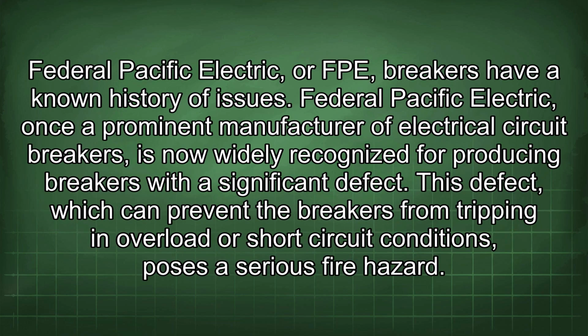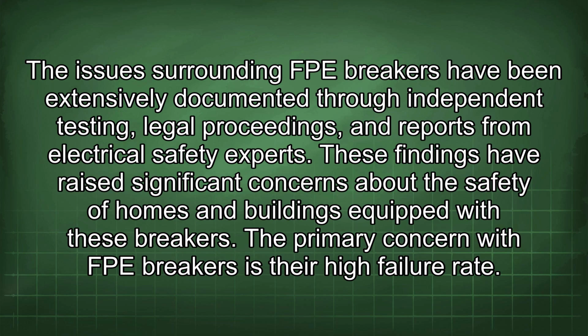Federal Pacific Electric, or FPE, breakers have a known history of issues. Federal Pacific Electric, once a prominent manufacturer of electrical circuit breakers, is now widely recognized for producing breakers with a significant defect. This defect, which can prevent the breakers from tripping in overload or short-circuit conditions, poses a serious fire hazard. The issues surrounding FPE breakers have been extensively documented through independent testing, legal proceedings, and reports from electrical safety experts. These findings have raised significant concerns about the safety of homes and buildings equipped with these breakers.